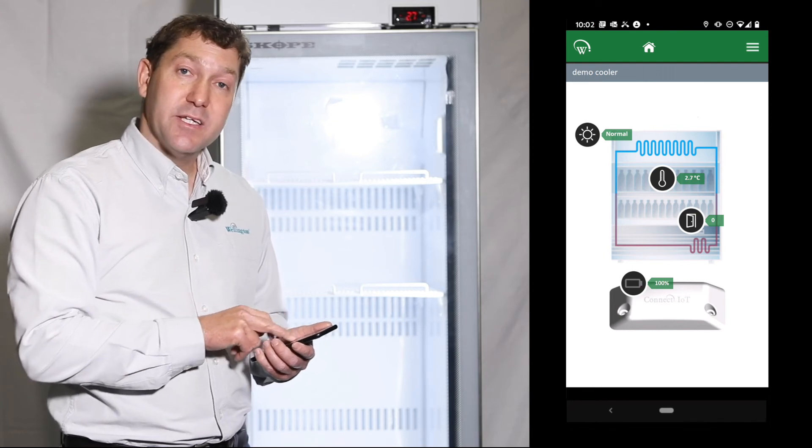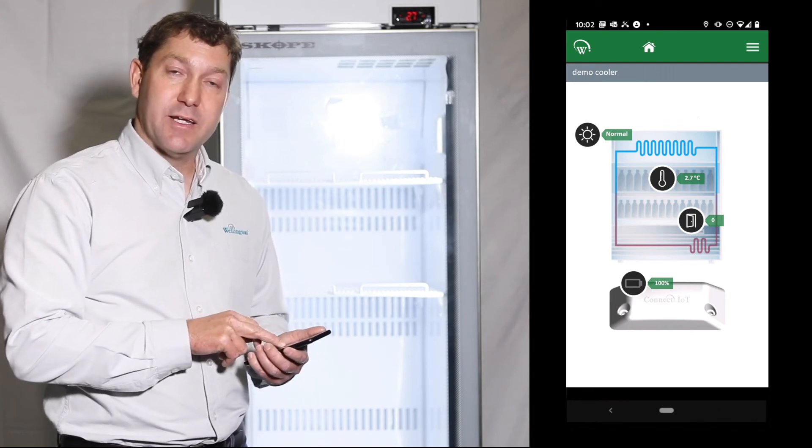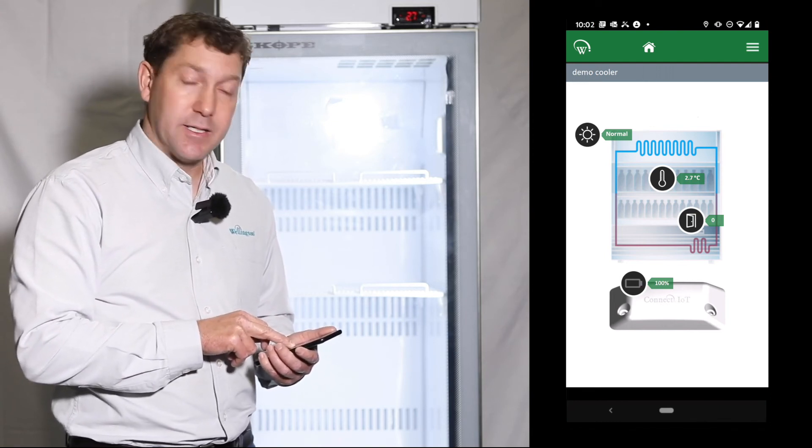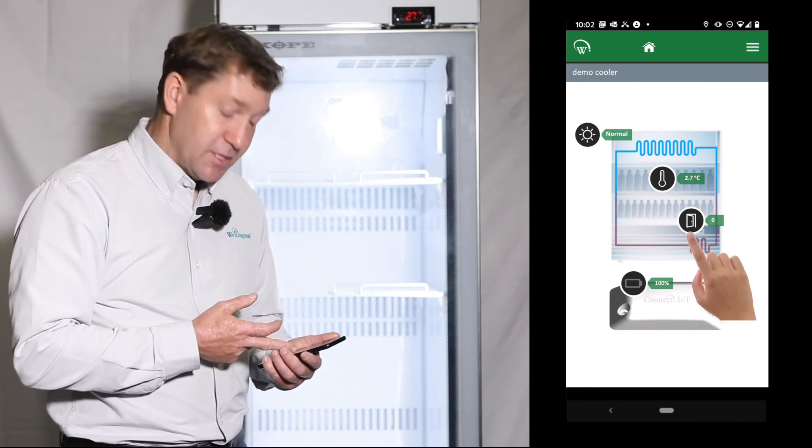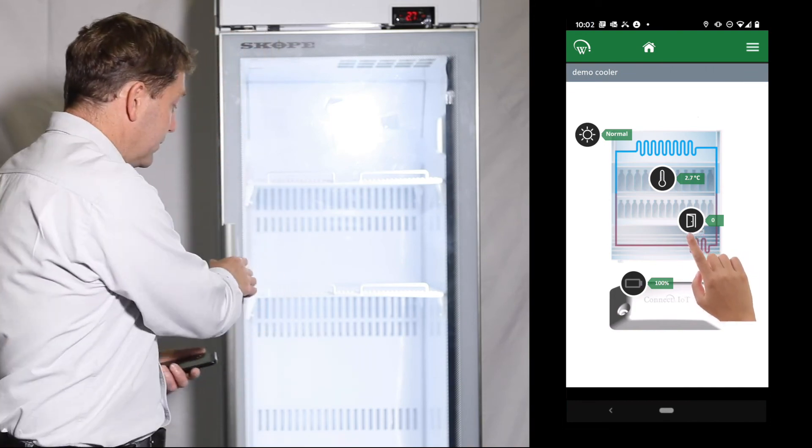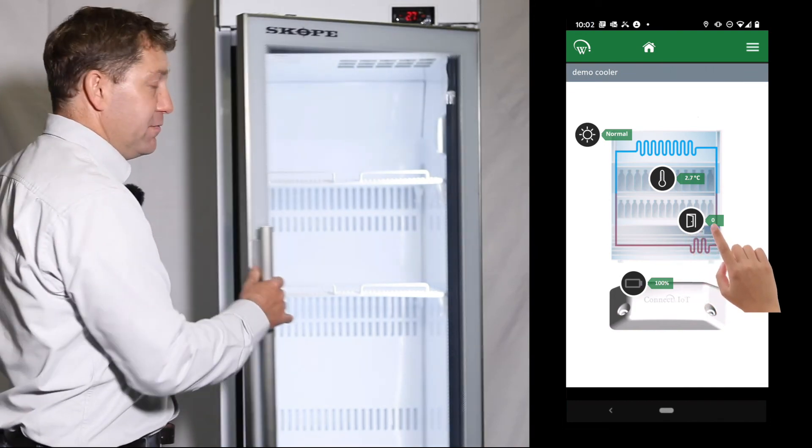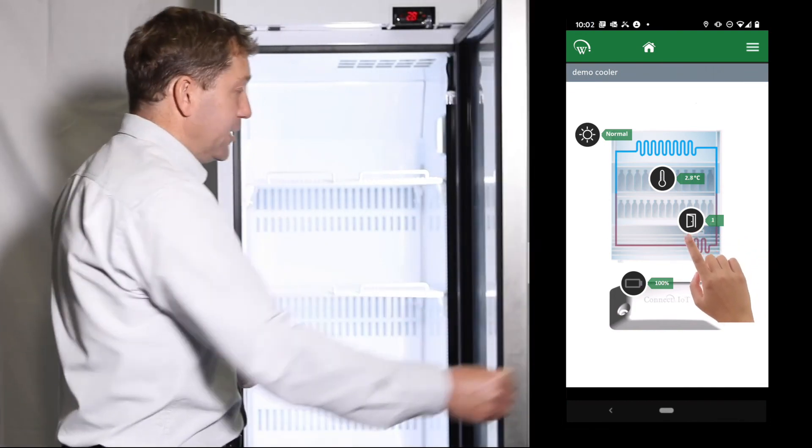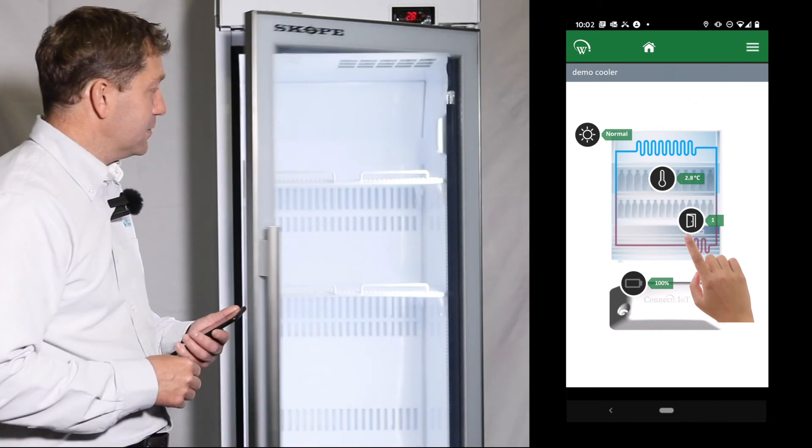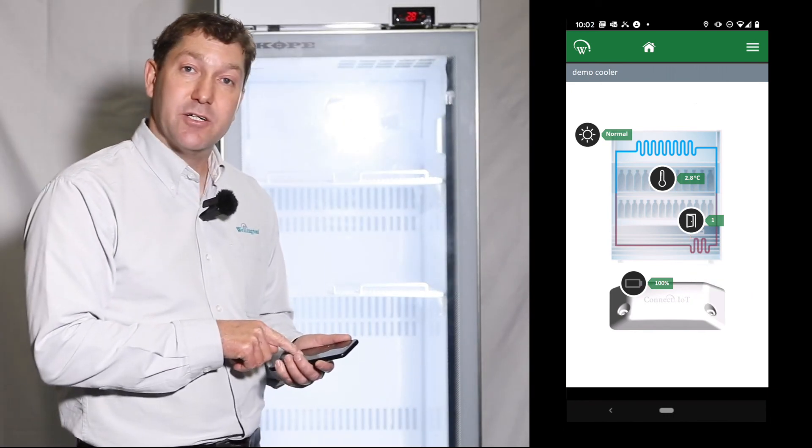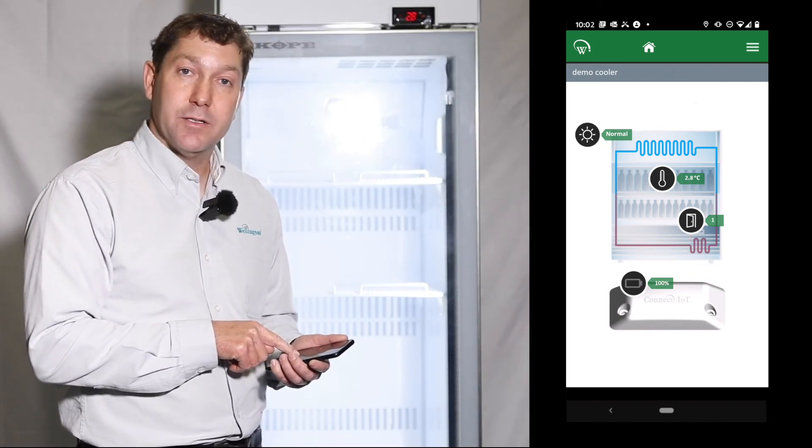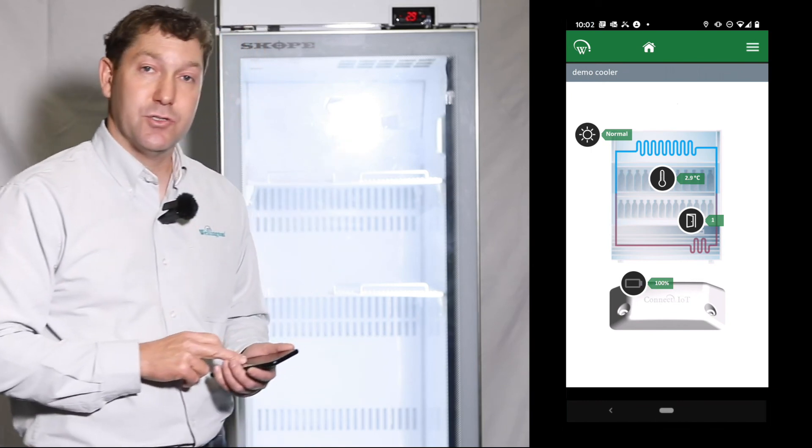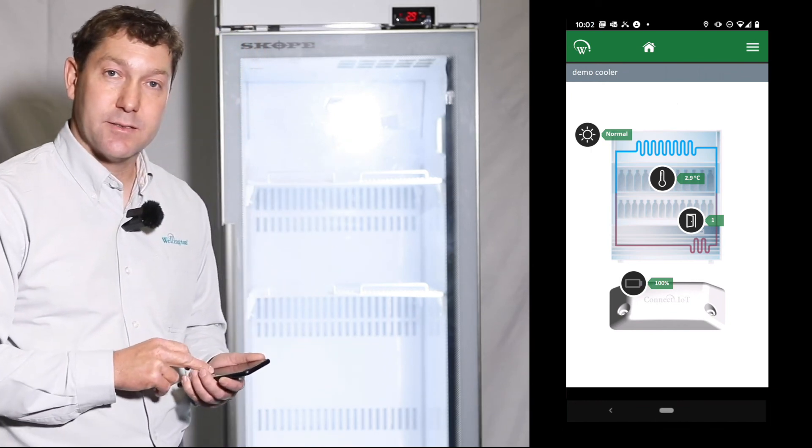The other thing that we then want to validate is the door openings are working correctly. So if you see the door opening count in the field app, if I open the door and then close it, we can see that the count is incremented by one. So that's showing that we're detecting door openings.